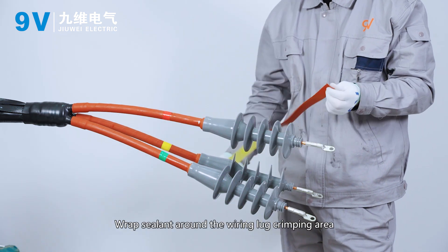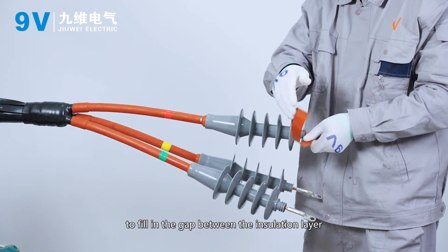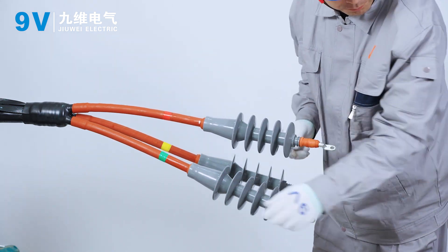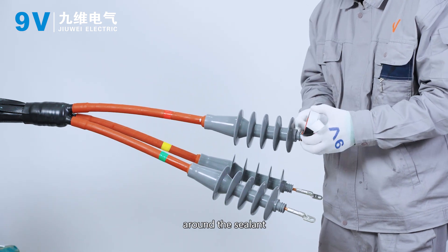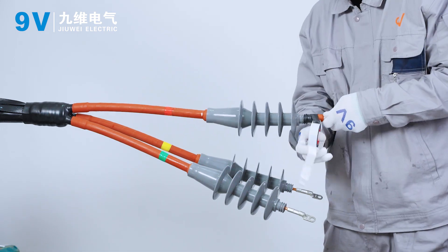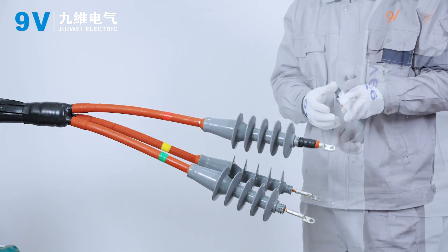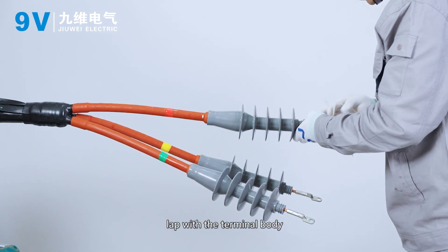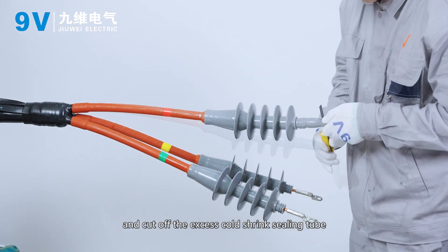Wrap sealant around the wiring lug crimping area to fill in the gap between the insulation layer and the lug indentation. Wrap a layer of insulating self-adhesive tape around the sealant. Cover the cold shrink sealing tube, lap with the terminal body, and cut off the excess cold shrink sealing tube.